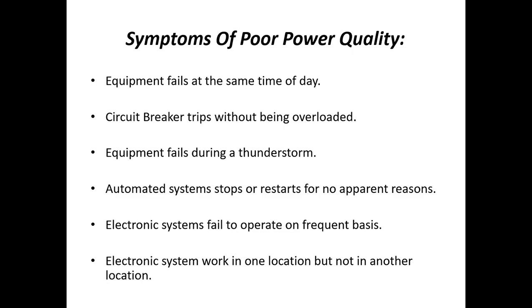Automated systems stop or restart for no apparent reason. If the automated system uses relays or some automatic system where we give threshold values of current and voltage, and poor power quality is there, the best example being higher or lower voltage, which may happen for some reasons, then the automated system starts and restarts continuously without any reason. Suppose the current we take is 10 ampere, and for a fraction of a second it goes to 11 ampere and then regains its position. Because of that, you will get frequent operation failure of that particular automated system.